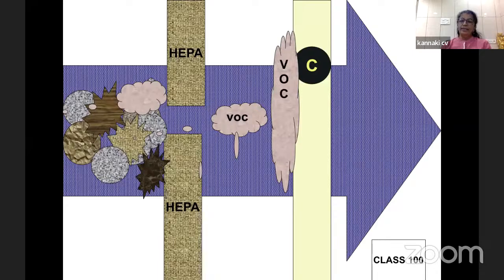So I've written there class 100. When you have laser counters, the people who do the air handling unit will have the laser counters, and you have to periodically check your room. What is the number of particles in a cubic foot of air? If it has 100, then it's a class 100 room. If it has 1,000, then it's a class 1,000 room.